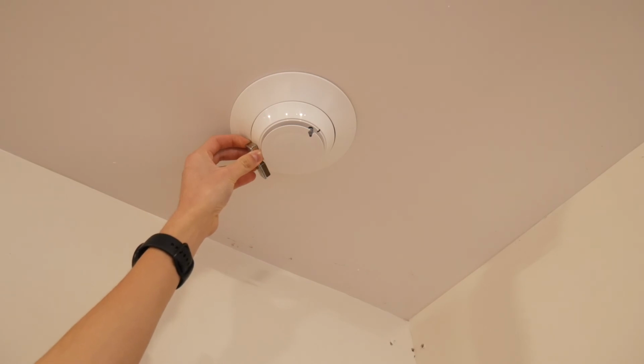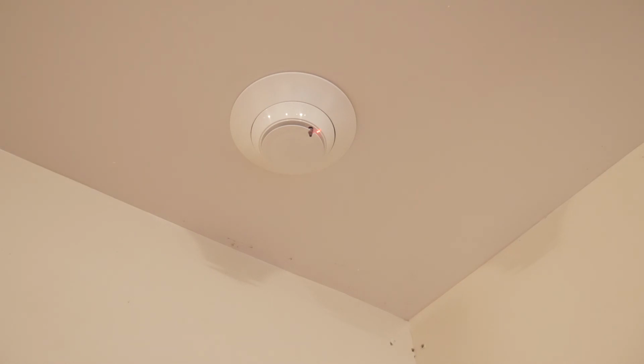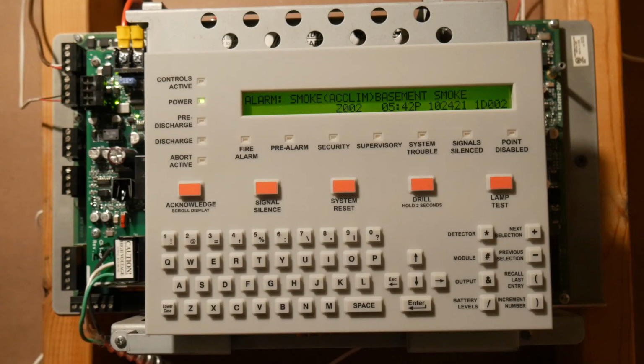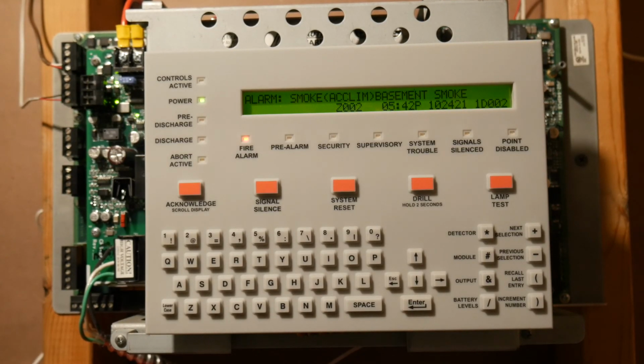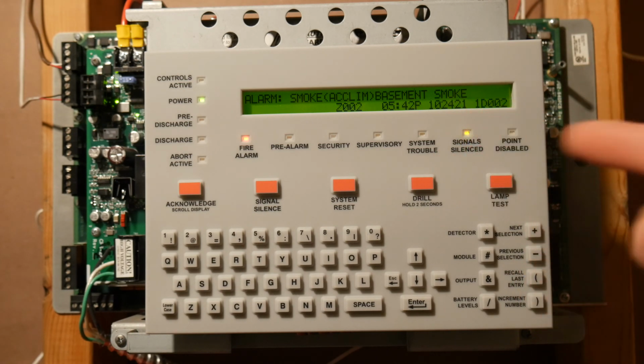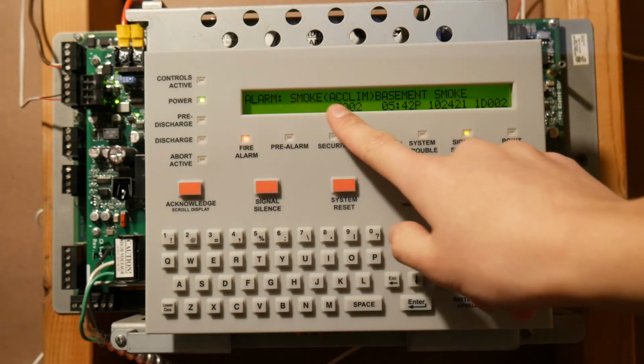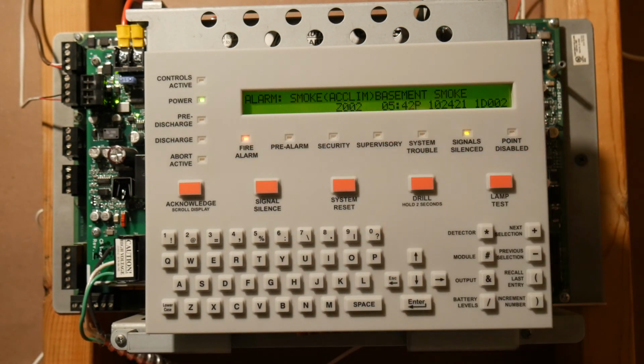Okay, it should be going to alarm soon. And it's in alarm. So I'll go back to the panel. Okay, I'm gonna press silence. Okay, the strobes are still flashing. I'm not sure if you can see, but yeah, they're still flashing. Also, you can see it says signal silence, fire alarm. It's a smoke detector. It's saying basement smoke, zone 2, and it activated at 5:42 p.m. So we're going to press system reset. And now we're going to test a module next. So I'll cut to that.